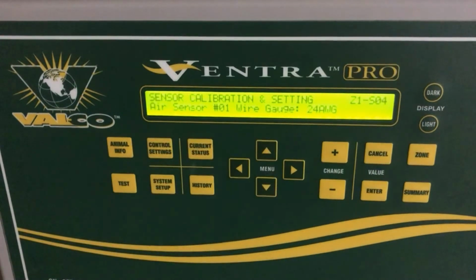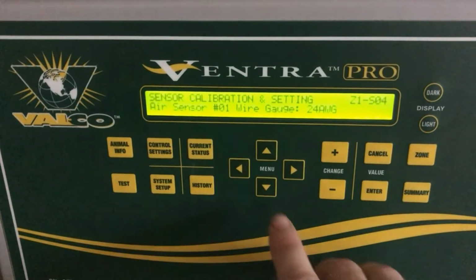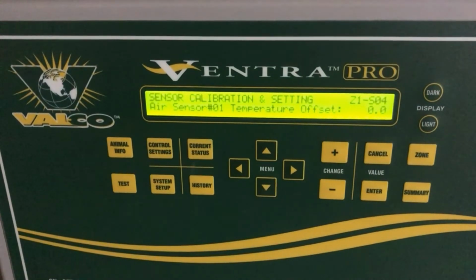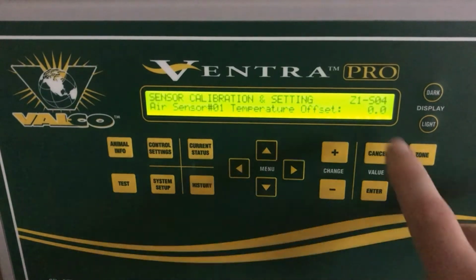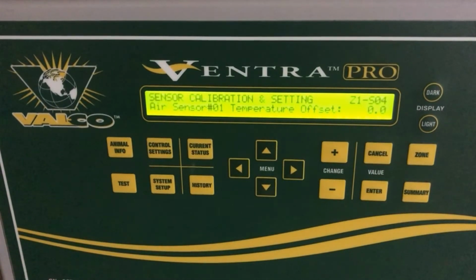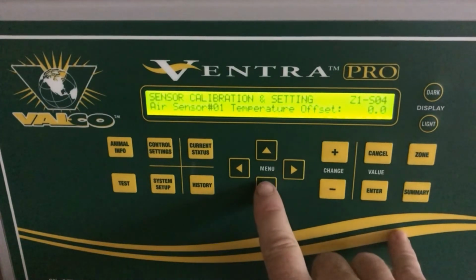Now you choose the wire gauge that you used. And in this case, we used 24 gauge, so we'll leave it there. Arrow down again. Now you have your temperature offset. Normally you will leave this at 0. The only reason you would not is if you have a temperature sensor that you have proven is not reading quite correct. You can put an adjustment in there, either plus or minus, to help the temperature sensor read the appropriate temperature in the area in which it's at.